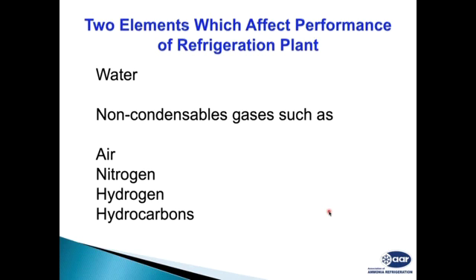So water and the non-condensable gas, or the air, which contributes a major part of it, affects our refrigeration system. Unfortunately, it does not affect it in a good way, as it does for the human being. Water and air, we know, are very good and essential for us, but they are not required in our refrigeration system. The air is considered a non-condensable gas along with nitrogen, hydrogen, and hydrocarbons in an ammonia refrigeration system, particularly because in our operating range of, say, -45 to plus 40 or 42 degree condensing, these non-condensable gases do not condense or evaporate. They remain throughout as gases, which do not give any refrigeration effect to us.